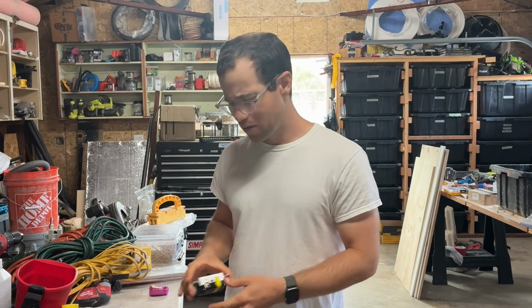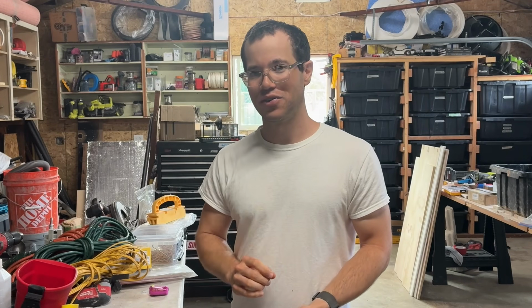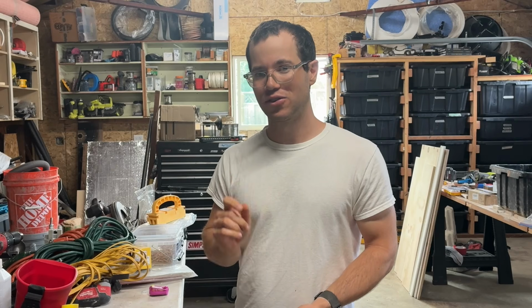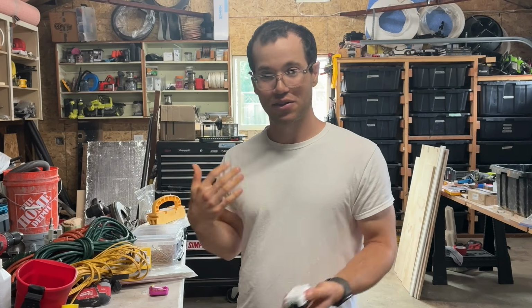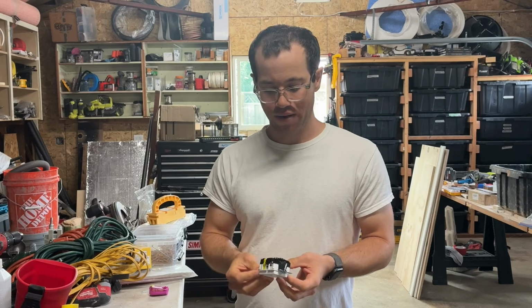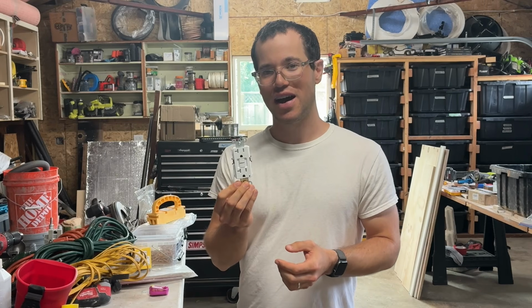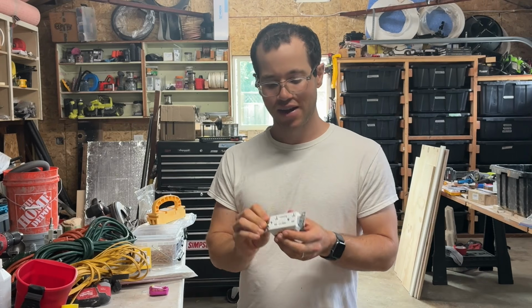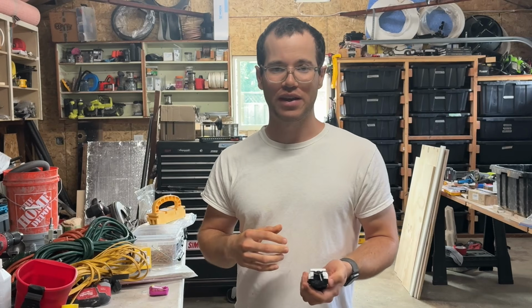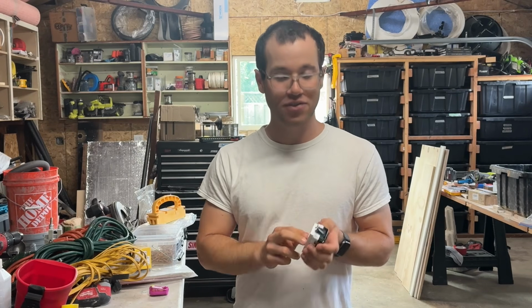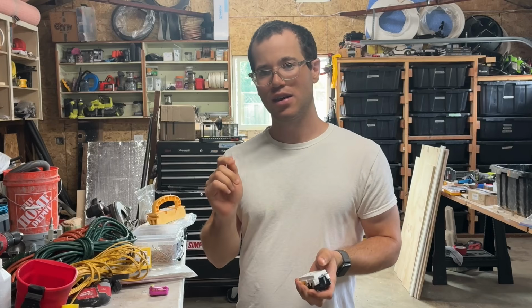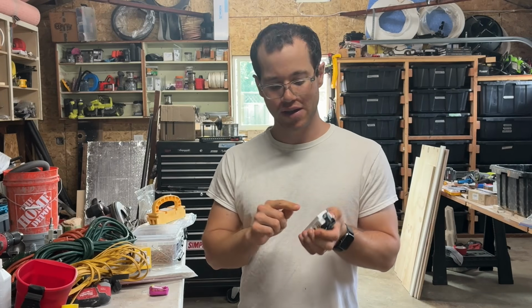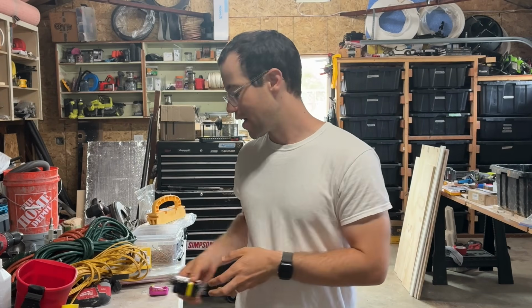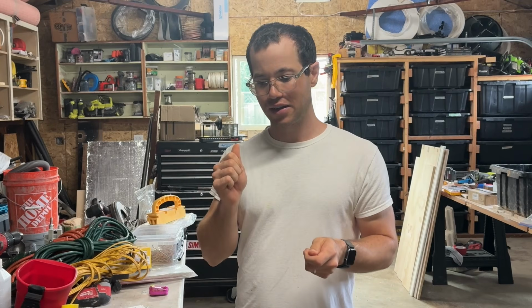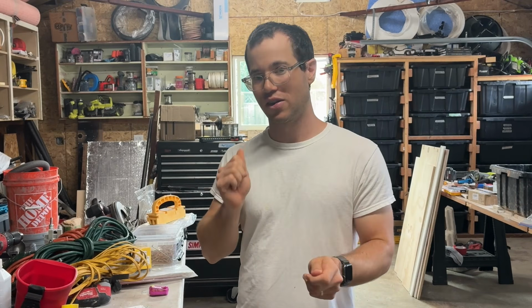So the NEC requires that ungrounded electrical circuits, like the two-wire circuits in our house, have GFCI outlets installed instead. These work by having a sensor that checks the amount of current flowing between the hot and neutral wire, and when there's a difference between the two, it shuts off.